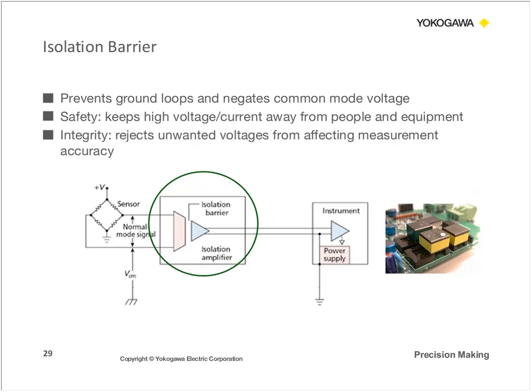Now, obviously, if you're working with a system design and you're able to implement internal isolation, that's going to be beneficial as well because it is the more cost-effective solution. But really, the main point of this isolation barrier is to interrupt that ground loop circuit. So it prevents current from flowing between your device and your instrument. And by breaking that ground loop, you negate the common mode noise as well as any other unwanted noise.